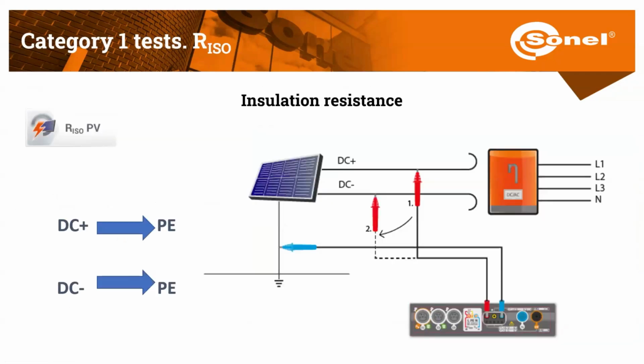Insulation resistance is the final test in the system. Most measuring devices perform this test in two steps. First, we check the insulation resistance between the positive pole and earth, like here. First positive to earth, then negative to earth.